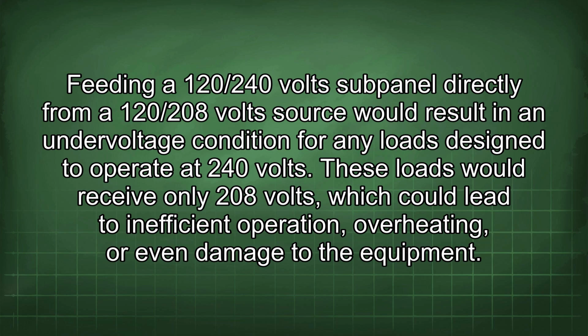Feeding a 120/240 volt subpanel directly from a 120/208 volt source would result in an undervoltage condition for any loads designed to operate at 240 volts. These loads would receive only 208 volts, which could lead to inefficient operation, overheating, or even damage to the equipment.